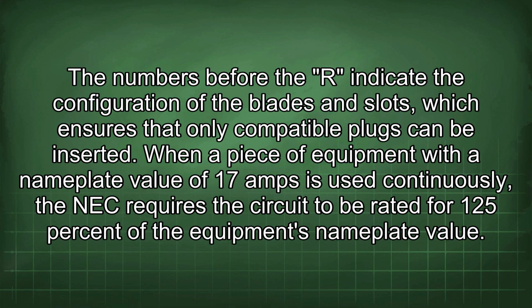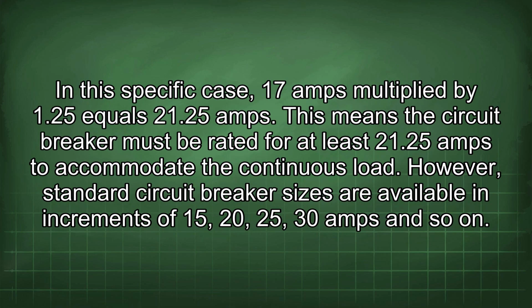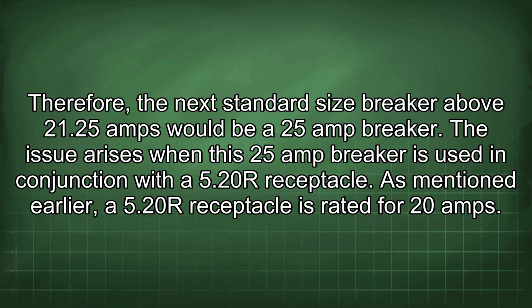can be inserted. When a piece of equipment with a nameplate value of 17 amps is used continuously, the NEC requires the circuit to be rated for 125% of the equipment's nameplate value. In this specific case, 17 amps multiplied by 1.25 equals 21.25 amps. This means the circuit breaker must be rated for at least 21.25 amps to accommodate the continuous load. However, standard circuit breaker sizes are available in increments of 15, 20, 25, 30 amps and so on. Therefore, the next standard size breaker above 21.25 amps would be a 25 amp breaker.